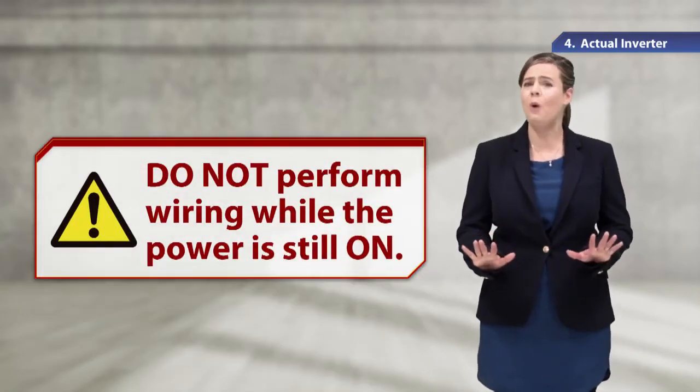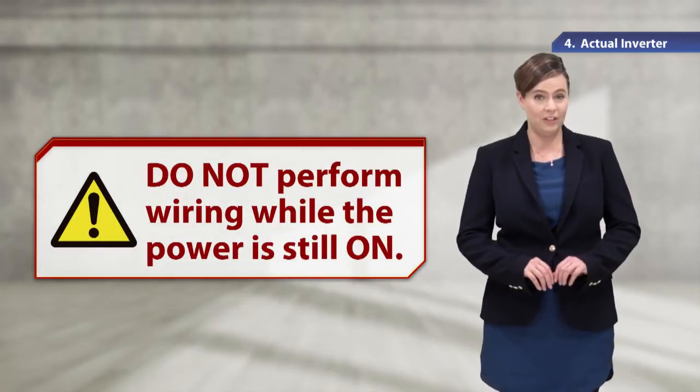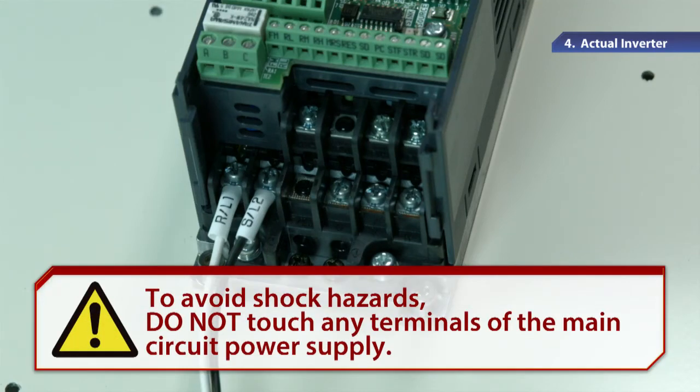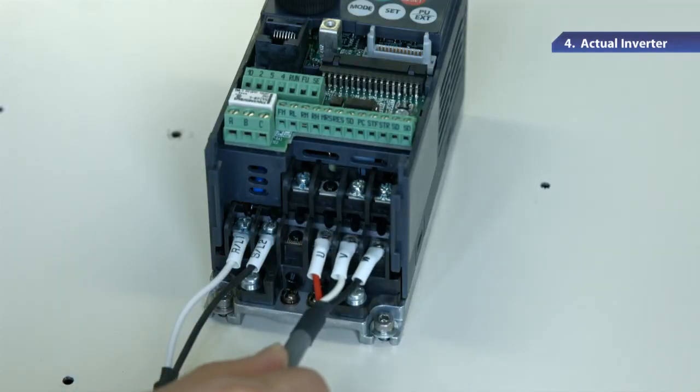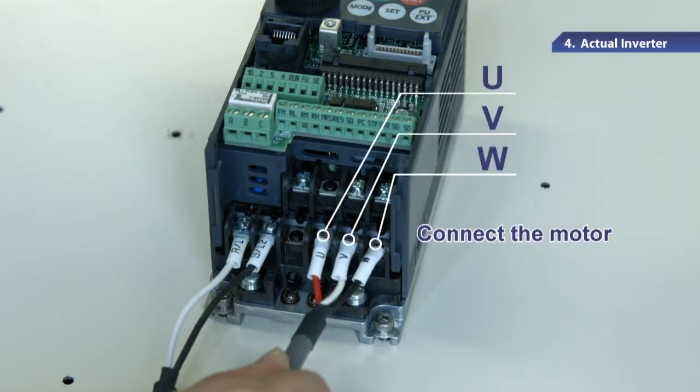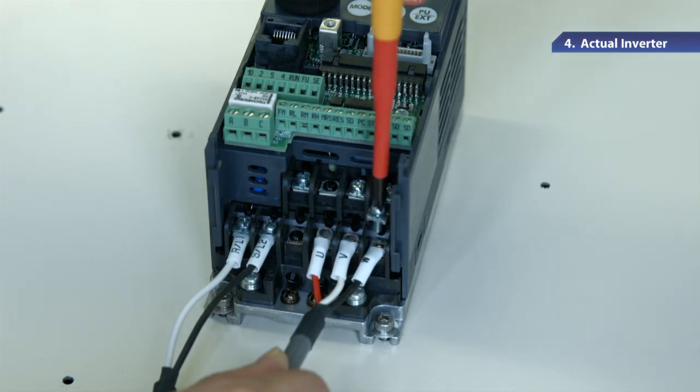Let's connect the motor next. Do not attempt any wiring work while the power is still on. To avoid shock hazards, do not touch any terminals of the main circuit power supply. Use the main circuit terminal U, V, and W of the inverter to connect the motor to the inverter.